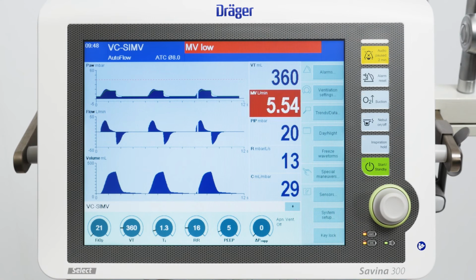Savina 300 Select displays the following visual and acoustic alarm signals. First, the system displays the relevant alarm message in the alarm message field of the header bar. Second, the parameter field of the parameter triggering the alarm flashes. Third, in the alarms dialog window, the corresponding measured value flashes. Fourth, for high priority or medium priority alarm messages, the corresponding LED flashes on the control panel.